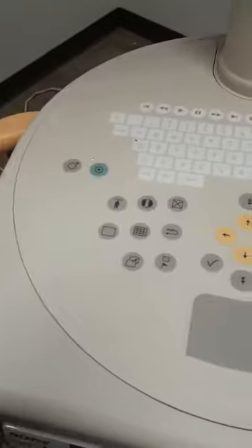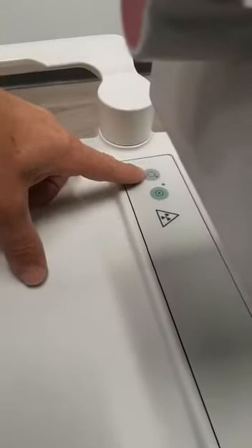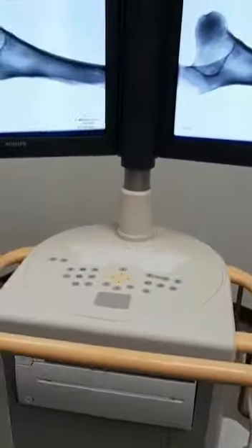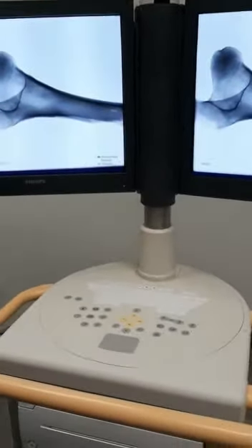You can also turn off just the mainframe alone if you want to do your post-processing and patient review. You can turn off the mainframe here. This will not turn off the workstation. This will leave the workstation on, but turn off the mainframe.